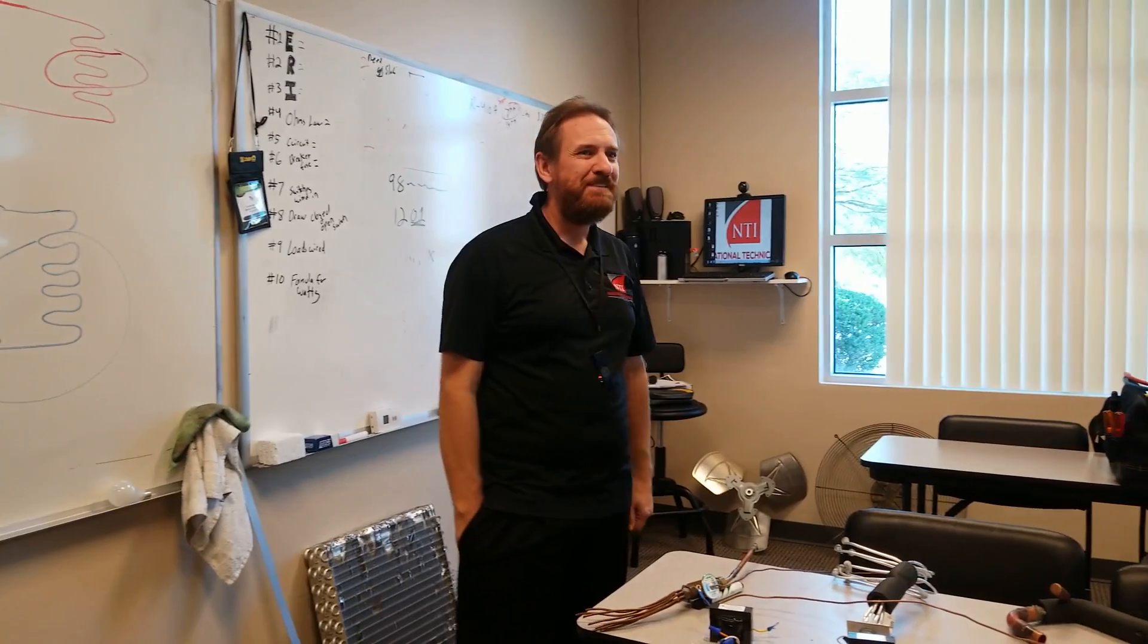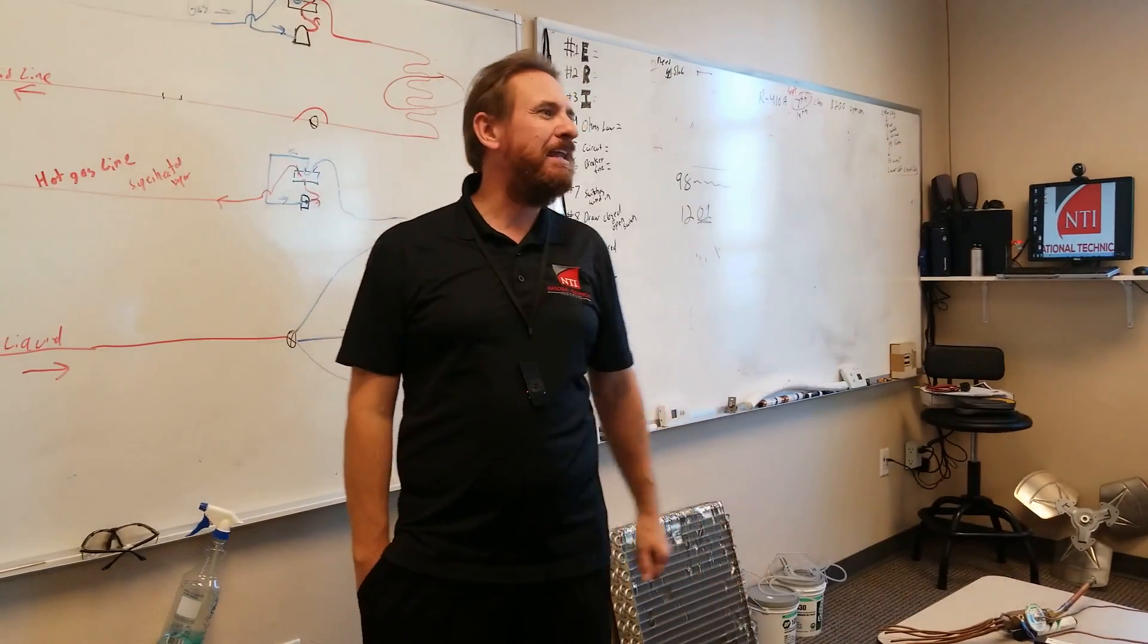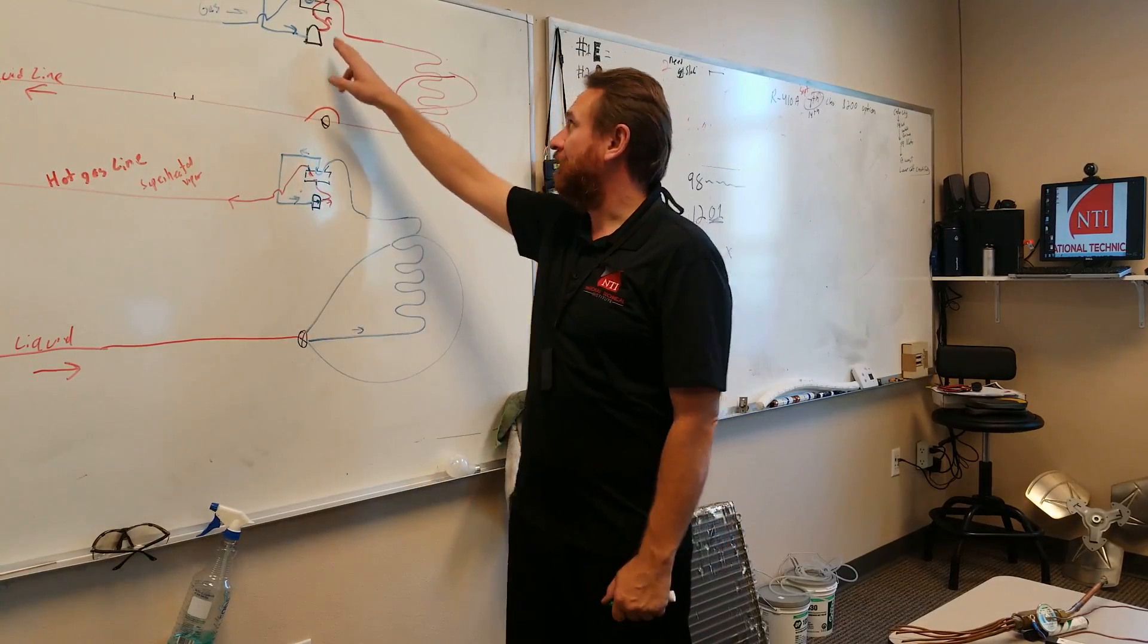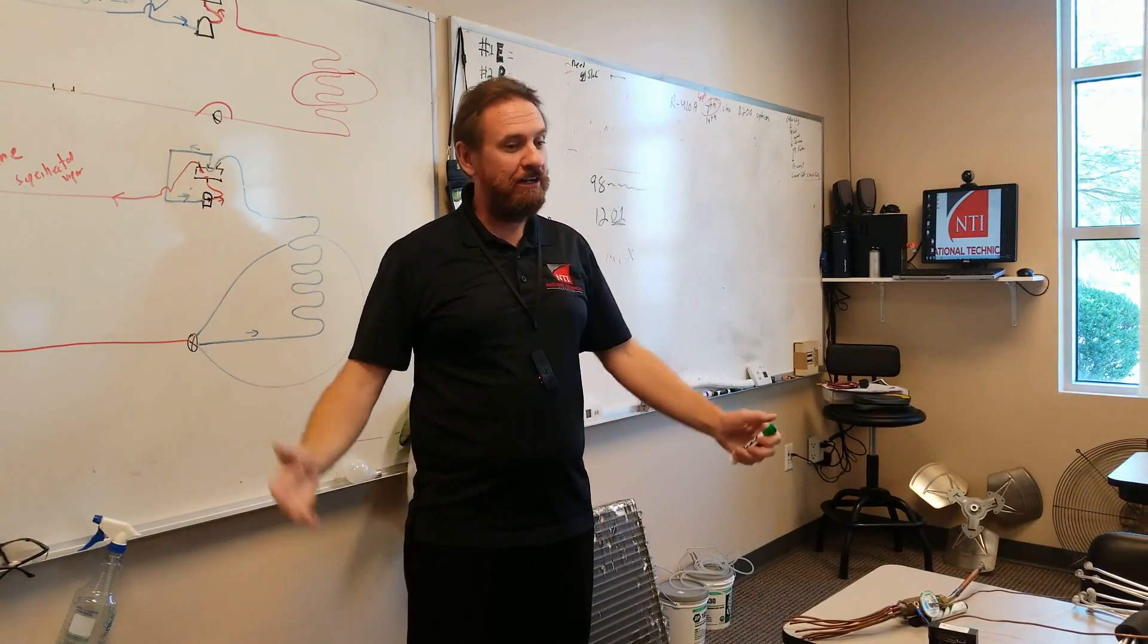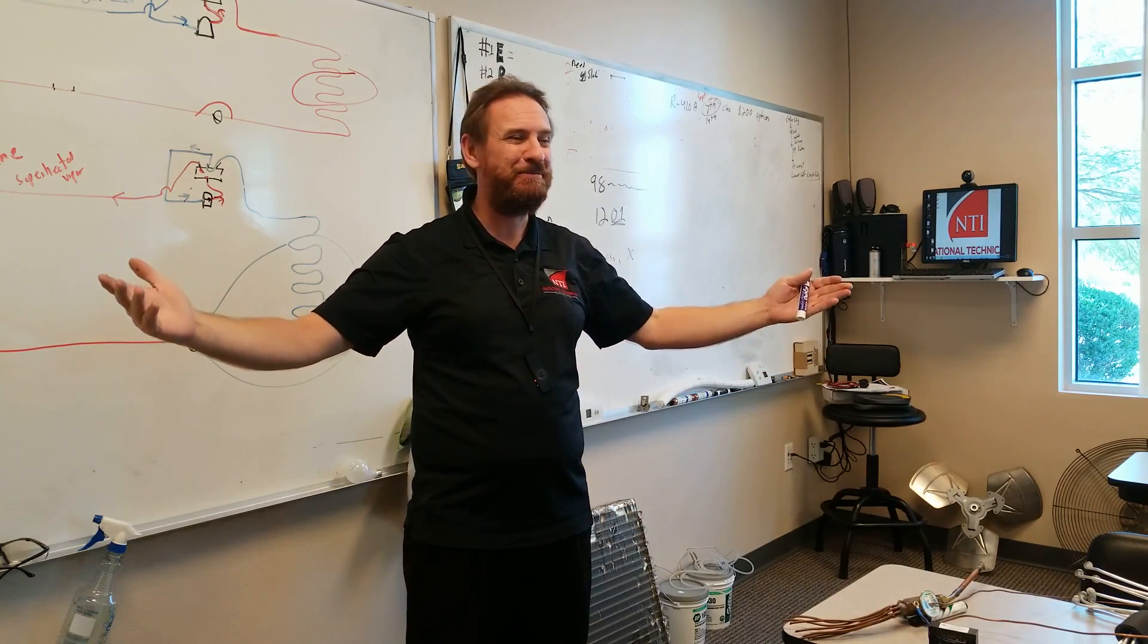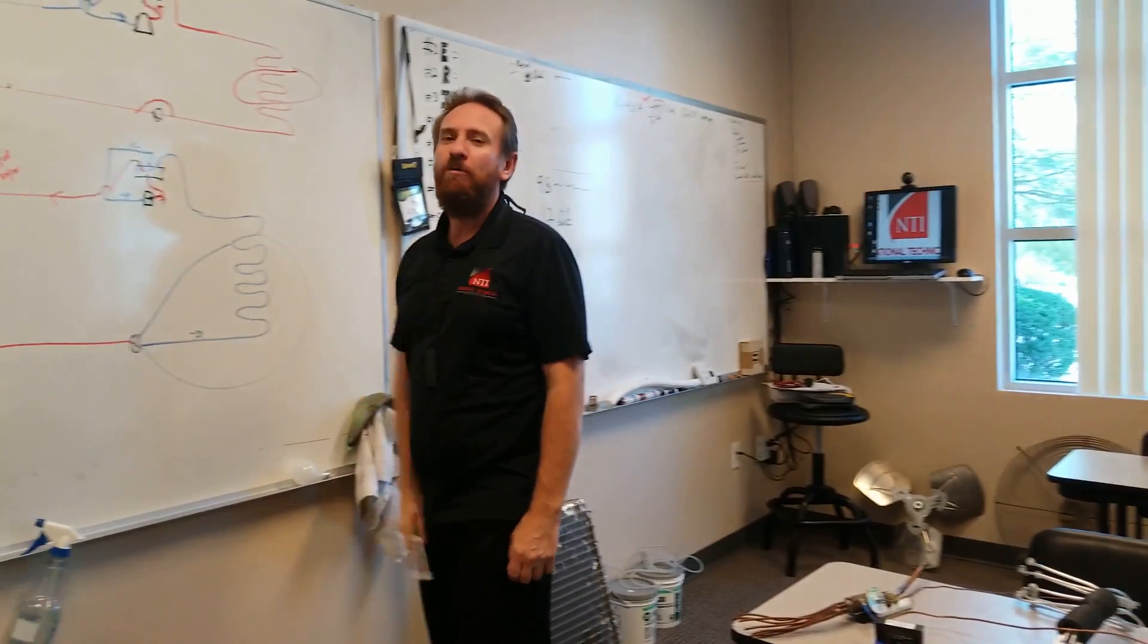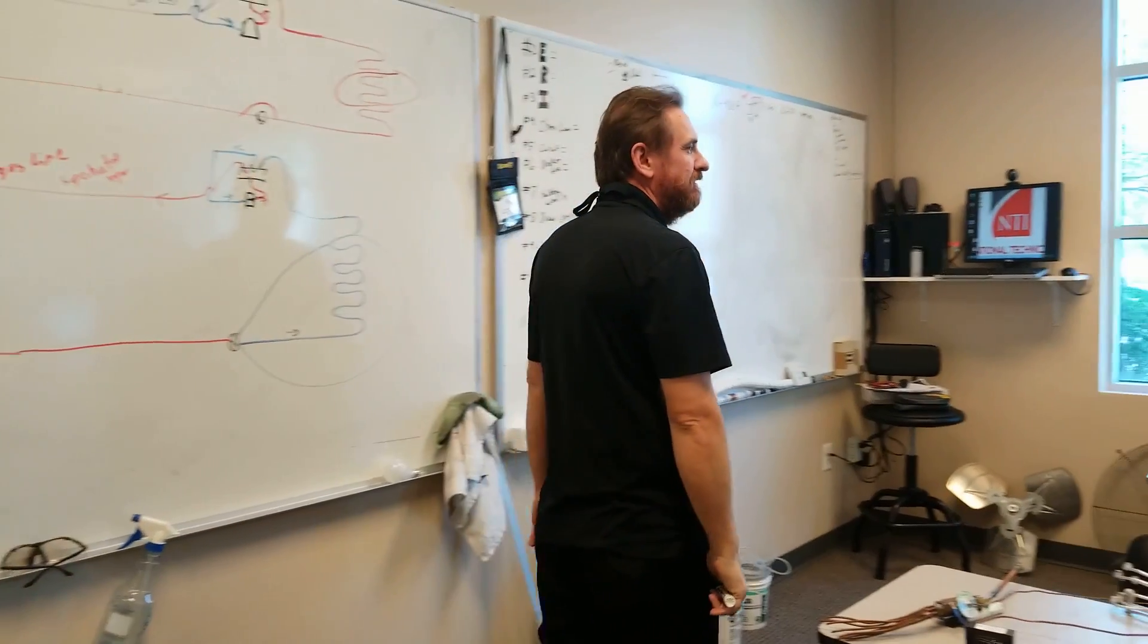So far, so good? That's a heat pump. Now, people make heat pumps way more complicated than there are. Sometimes people go to a unit and they don't know what's wrong with the unit. And they look at that reversing valve and they don't know how the reversing valve works. And you're like, well, I don't know the problem. I don't know what this does. That has to be the problem. Notoriously, people want to replace the reversing valve when the reversing valve has nothing wrong with it.